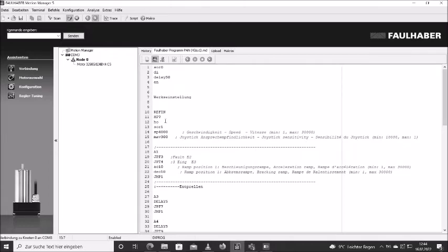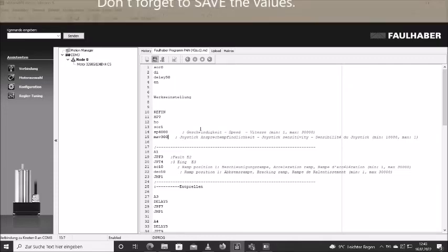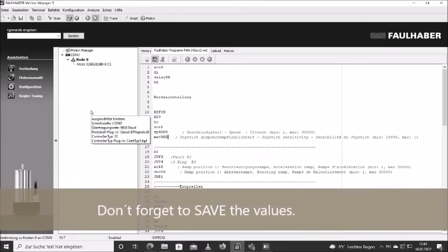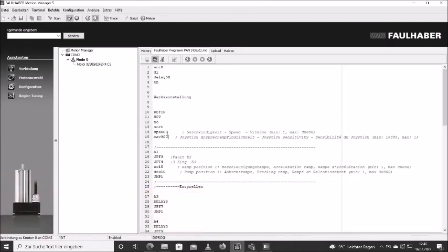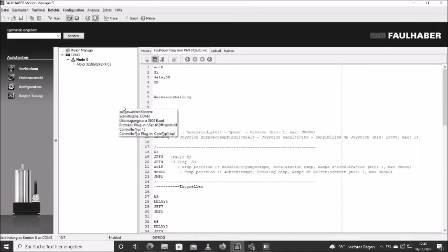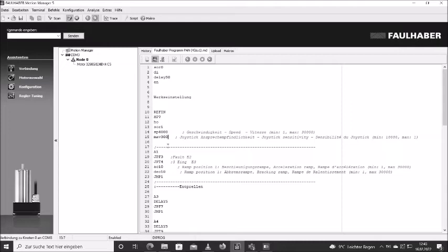So now this new program is on the remote head, but what is very crucial is we need to change the EEPROM, which is the memory of the remote head. We have three different commands that we have to type in in order to actually save the new value. Otherwise, after switching off and on again, this new value would be set back to the old one.